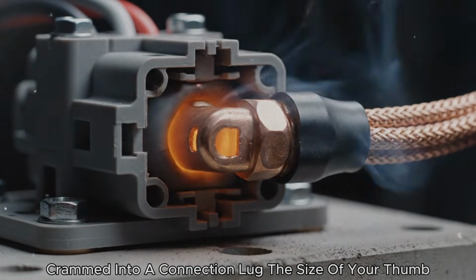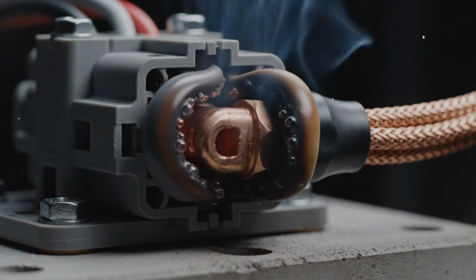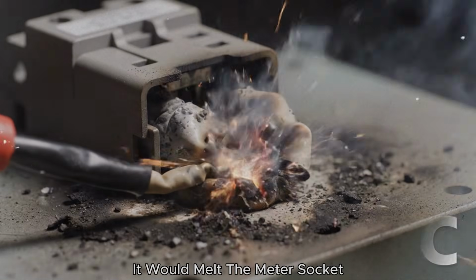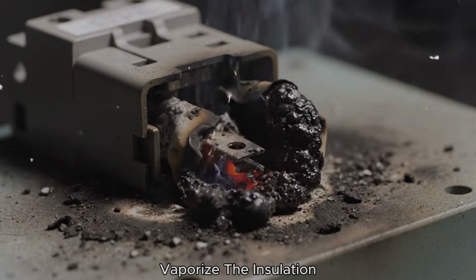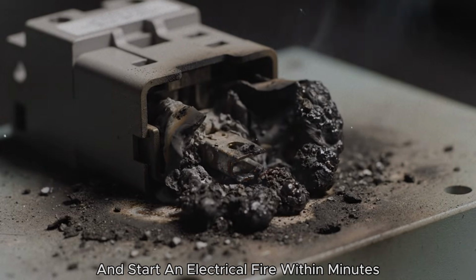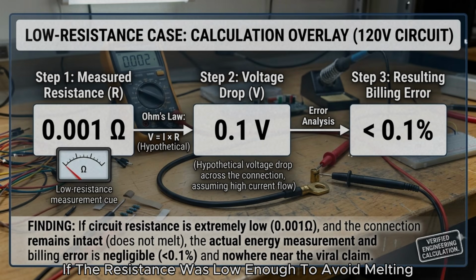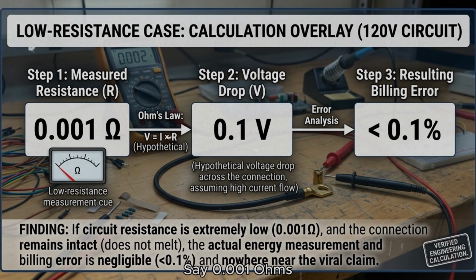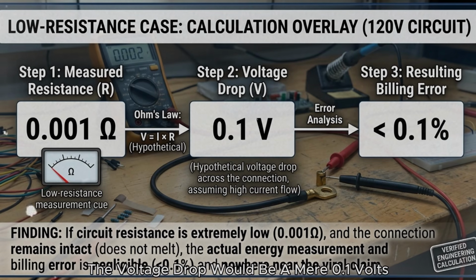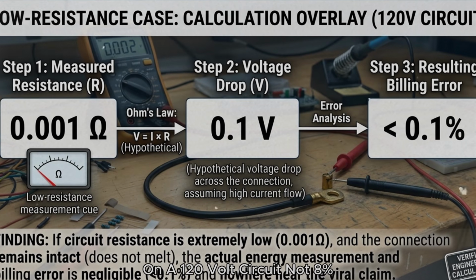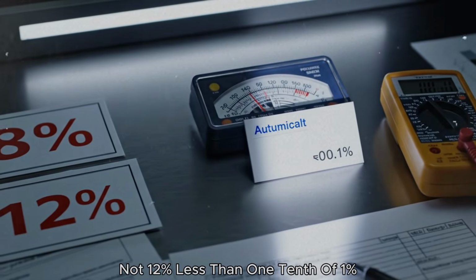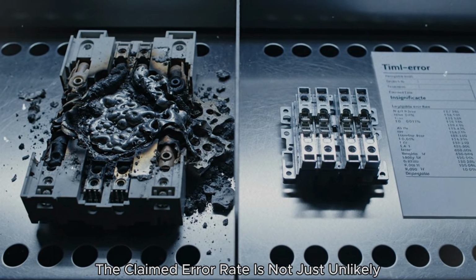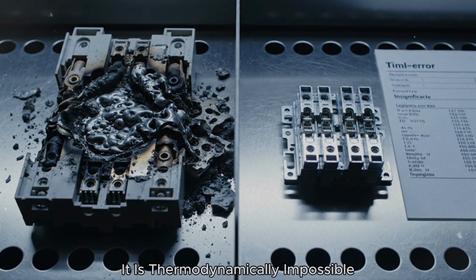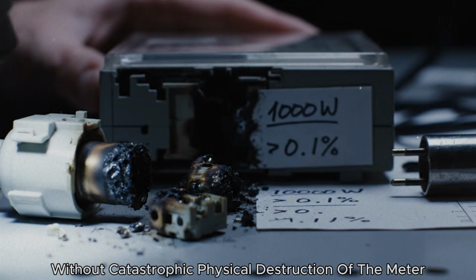Imagine a space heater crammed into a connection lug the size of your thumb. That terminal would not quietly overcharge you. It would melt the meter socket, vaporize the insulation, and start an electrical fire within minutes. If the resistance was low enough to avoid melting, say 0.001 ohms, the voltage drop would be a mere 0.1 volts, representing an error of less than 0.1% on a 120-volt circuit. Not 8%, not 12%, less than 0.1%. The claimed error rate is not just unlikely. It is thermodynamically impossible without catastrophic physical destruction of the meter.